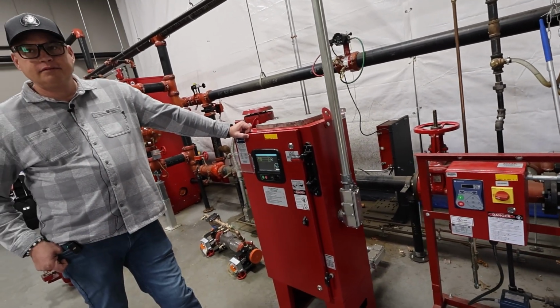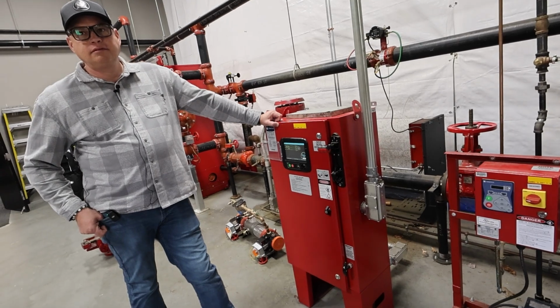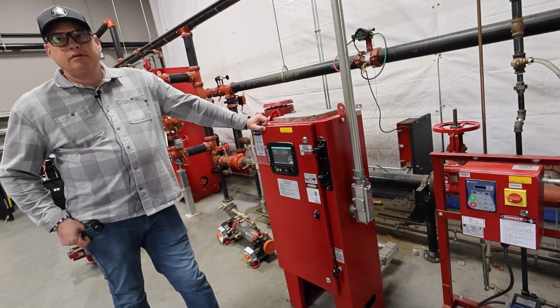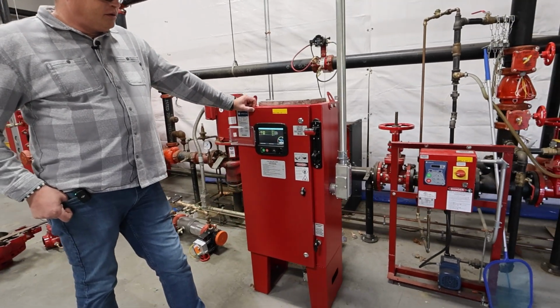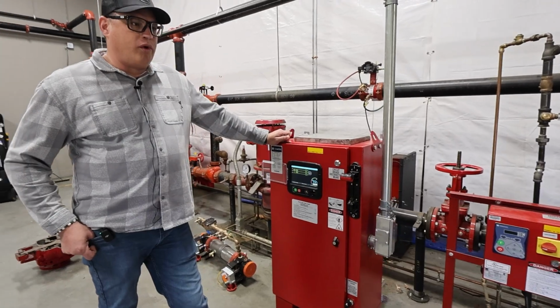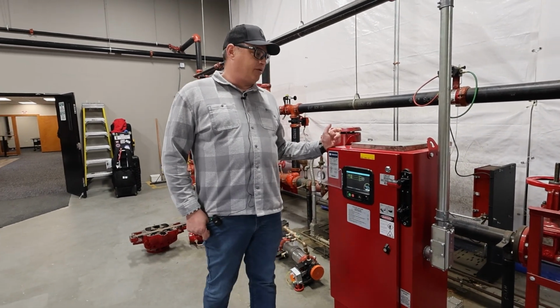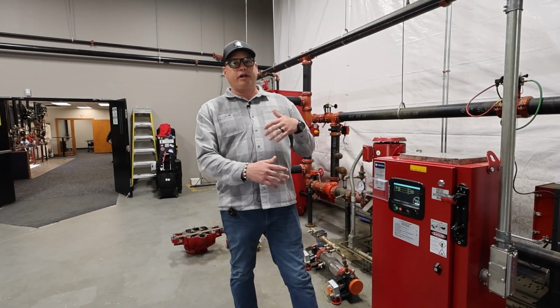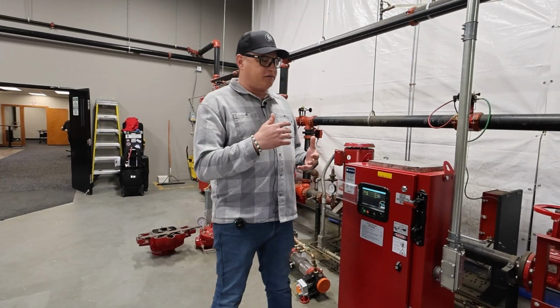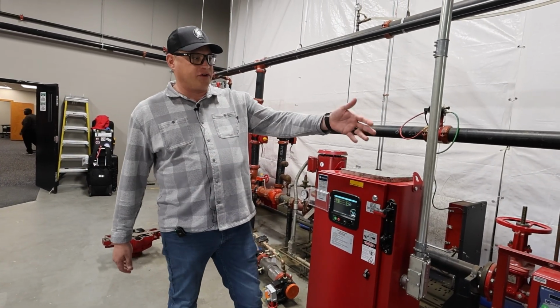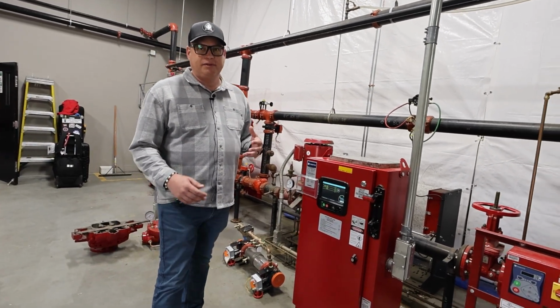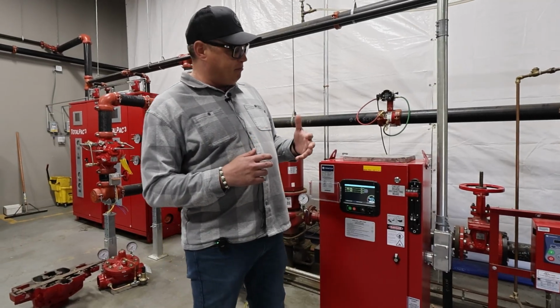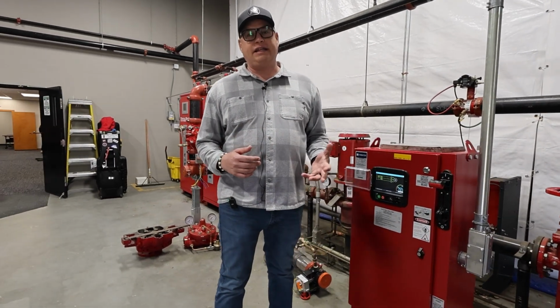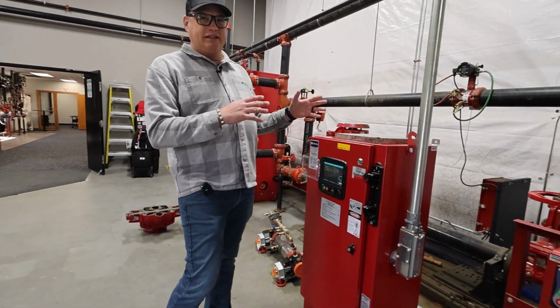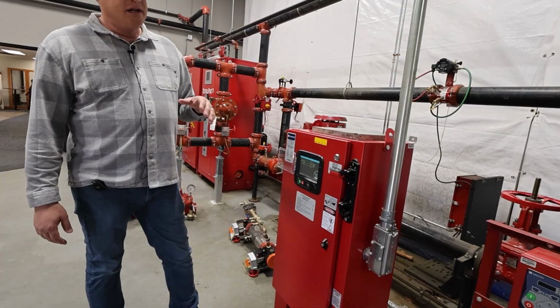Monthly tests, you may shut the discharge valve. I like to keep them open to test the system piping itself. But I know that's an option as well. Yeah, you don't want to recirculate water during a run test because the water will get really hot, and as you know, we have certain rubber components throughout the system that could then deteriorate, melt, and break down, and then cause leaks. Right. So that's a big reason they don't want the water recirculating.